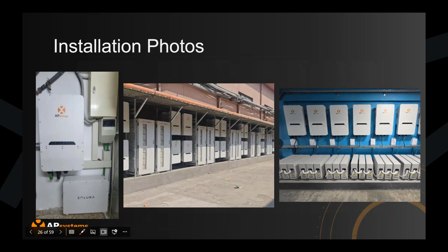Good question, the quick answer is yes. The reason is that from an inverter's perspective, it's only going to push power if it sees 240 on the AC side. There's also an additional nuance: when you go off grid, how do you turn off the solar to prevent overcharging of the battery? What we do is turn off the 240 if the battery gets close to full, to turn off the solar. Then when the battery is depleted and ready to accept more power, it turns 240 back on to start pushing power to the battery again.